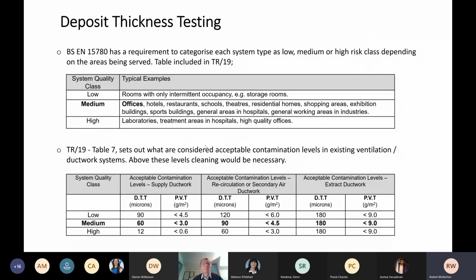So then we come on to the types of tests we would do within a ductwork system in terms of hygiene. When I was talking about BS 15780, which is incorporated into TR19, what that did was classify rooms and buildings. Here you can see low classified areas, that would be storage rooms, corridors, that sort of thing. Medium, offices, and this would for the most part cover most buildings and their usage. High, we've got labs, treatment areas in hospitals, also theatres, operating theatres, that sort of thing. So in accordance with those guidelines, we have these classifications.